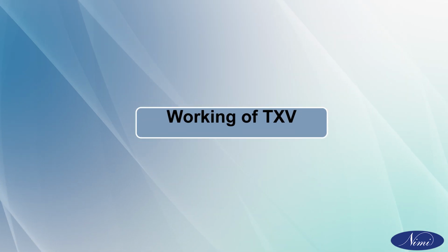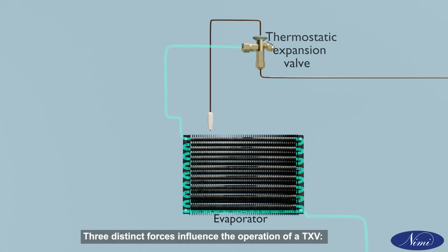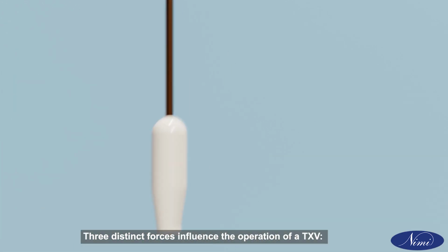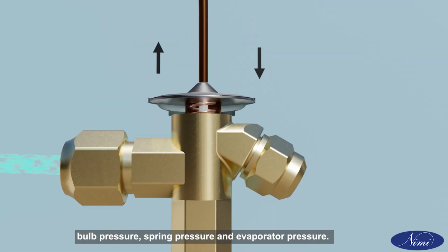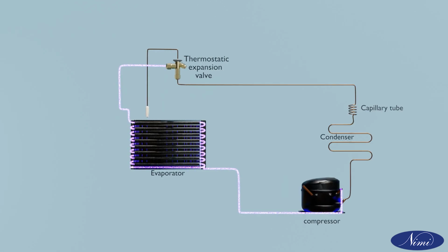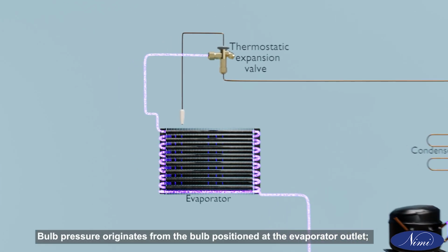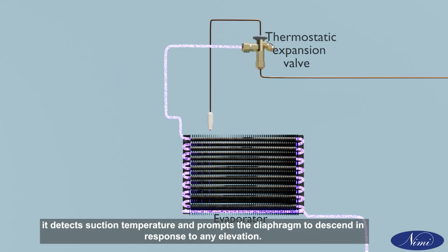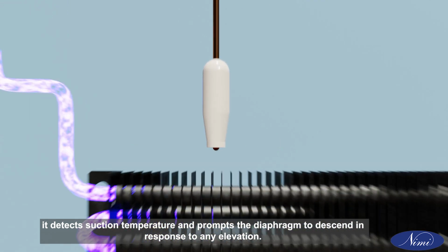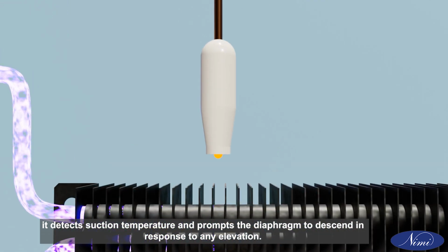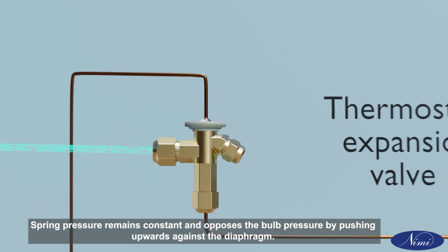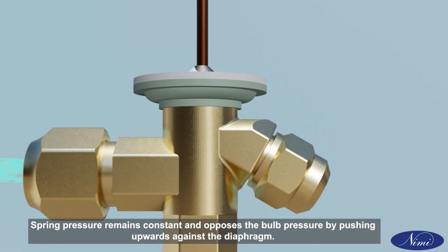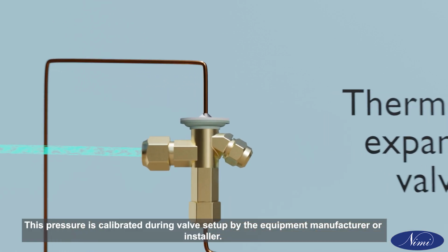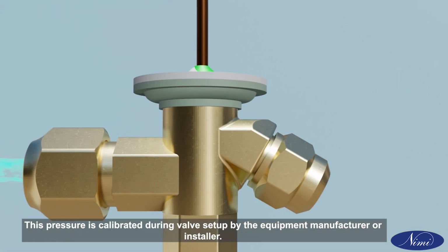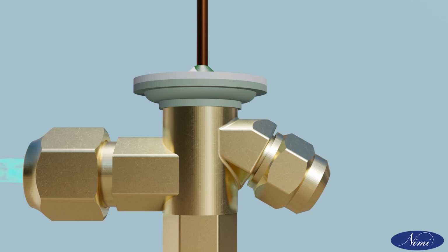Working of TXV. Three distinct forces influence the operation of a TXV: bulb pressure, spring pressure, and evaporator pressure. Bulb pressure originates from the bulb positioned at the evaporator outlet. It detects suction temperature and prompts the diaphragm to descend in response to any elevation. Spring pressure remains constant and opposes the bulb pressure by pushing upwards against the diaphragm. This pressure is calibrated during valve setup by the equipment manufacturer or installer.